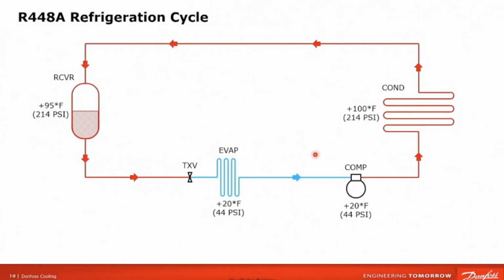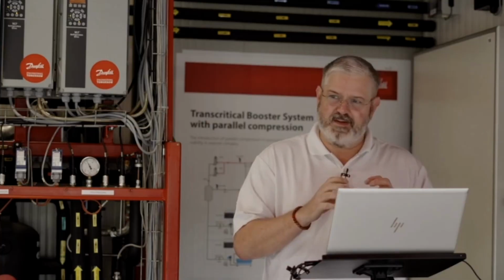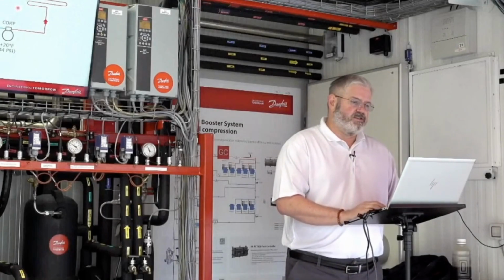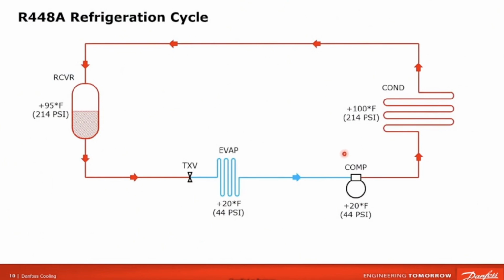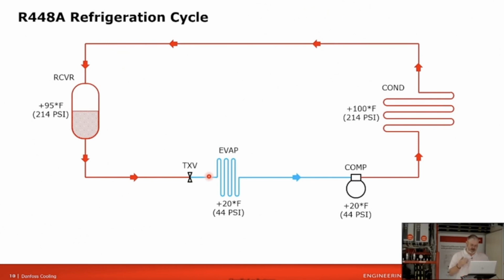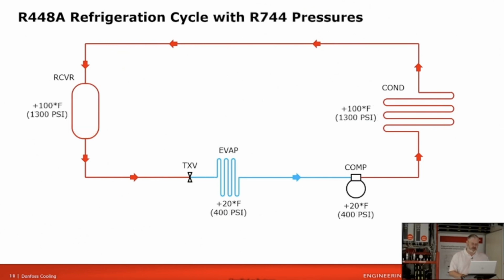So I'm going to explain the new components needed to handle CO₂ in the way that it makes sense to me. I like to learn things until they seem simple, so I'm going to try and explain it to you simply. So we're going to take a 448 HFC system, compressor, condenser, receiver, and evaporator, and we're going to assume that we just evacuated that system and charged it with CO₂. We did nothing other than evacuate it, take the same system, and put 744 in it. So a couple of things changed because of the 744. The first thing would be that our evaporator pressure and our medium temp suction pressures are now at 400 pounds instead of 44 that they were with 448A, which is pretty high for suction, as well as on a 100-degree day, we're now 1,300 pounds at the condenser.